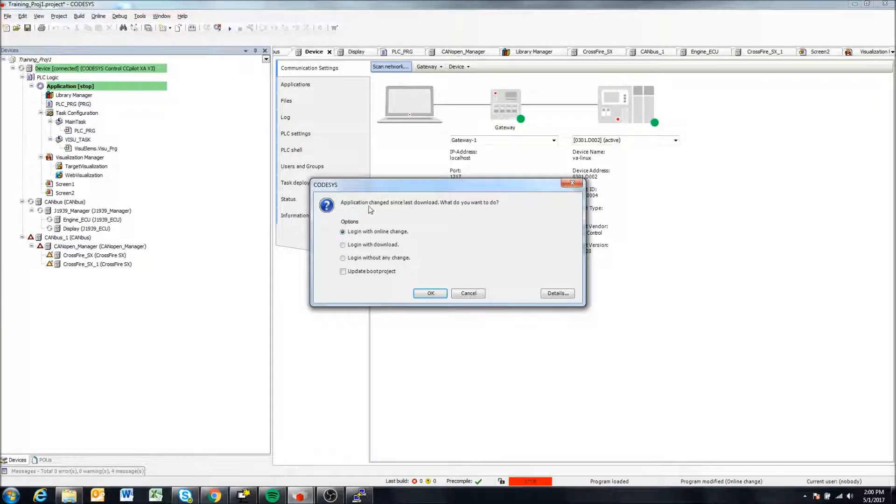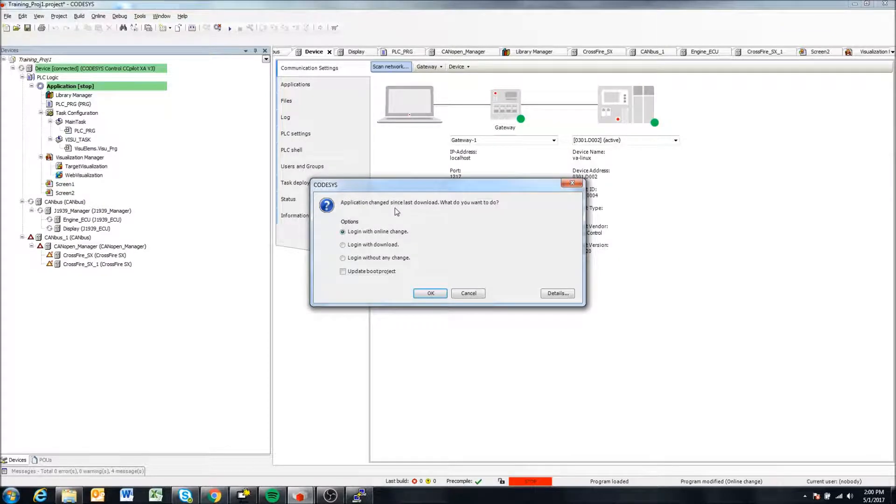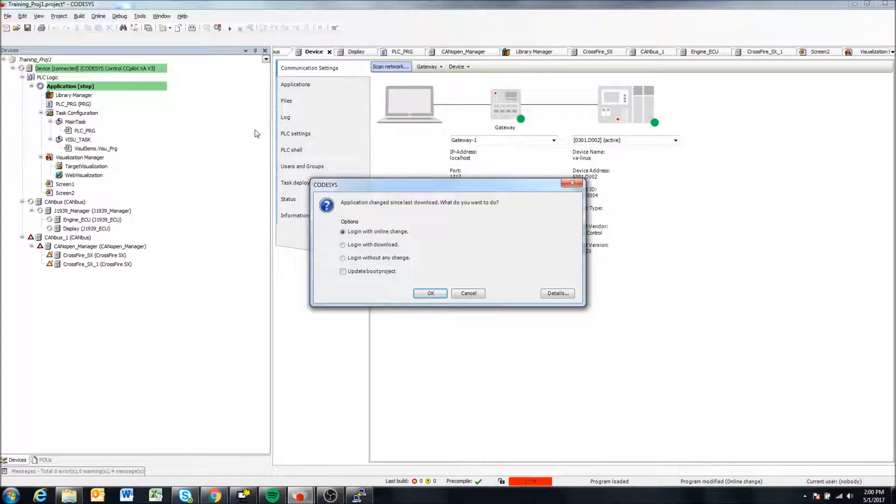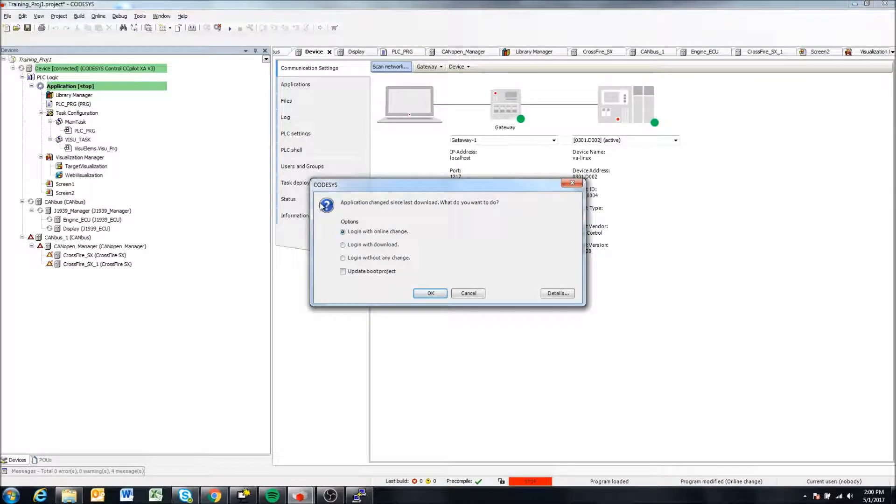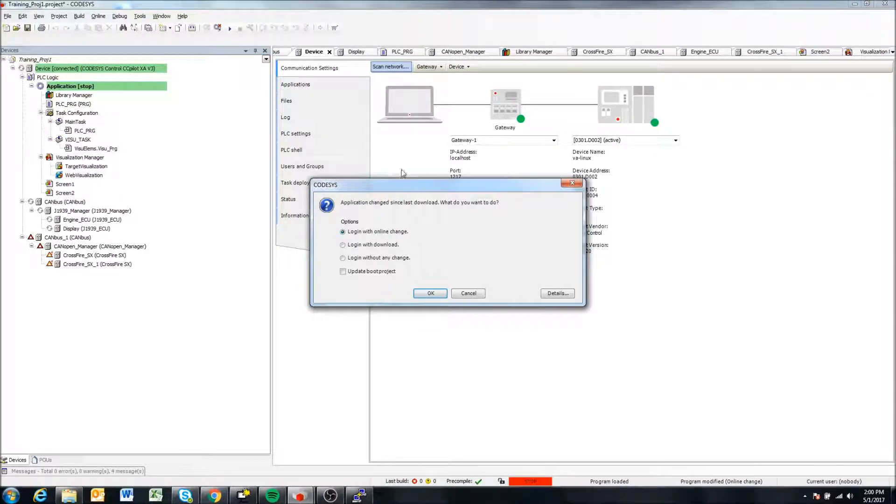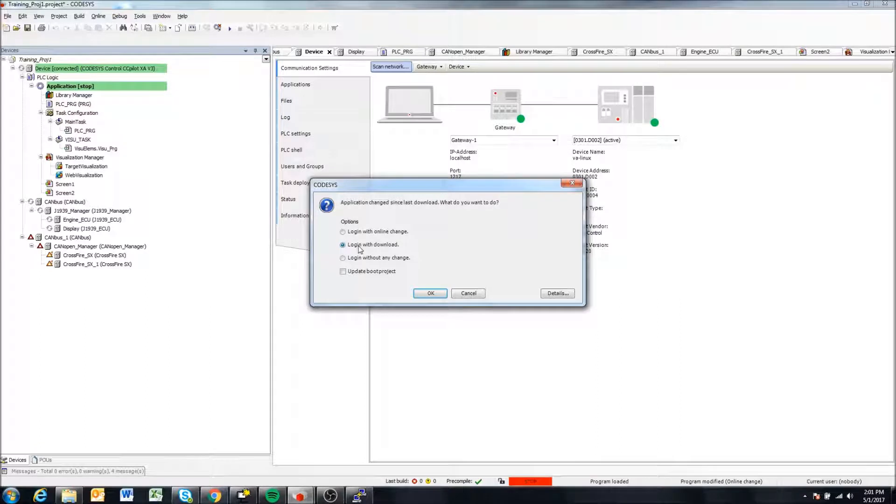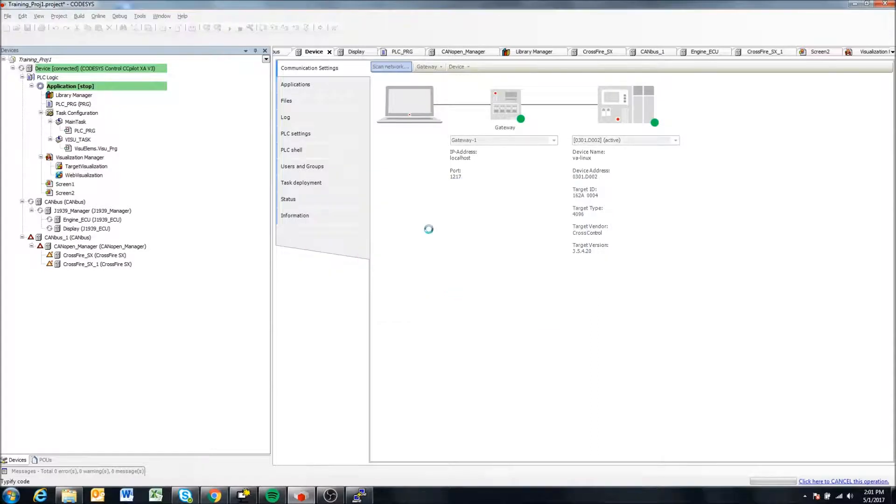So it tells me here, this is another warning message. It says it detects that the application I'm trying to load is the same application, but that I've made changes to it in my development environment here. I've made changes to it since the last one that was loaded and downloaded to the display. So here I can say log in with download. And this is going to re-download the change project and run that.